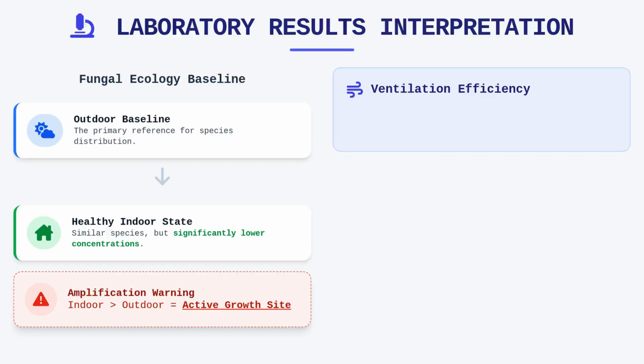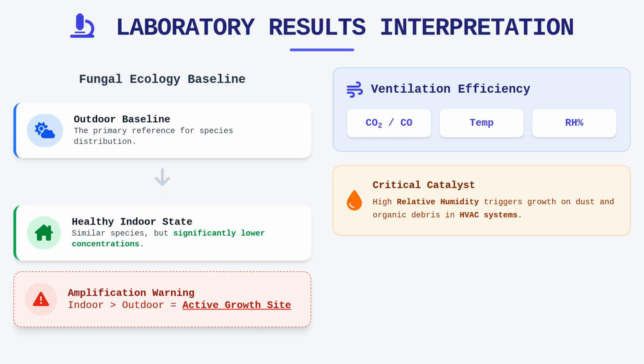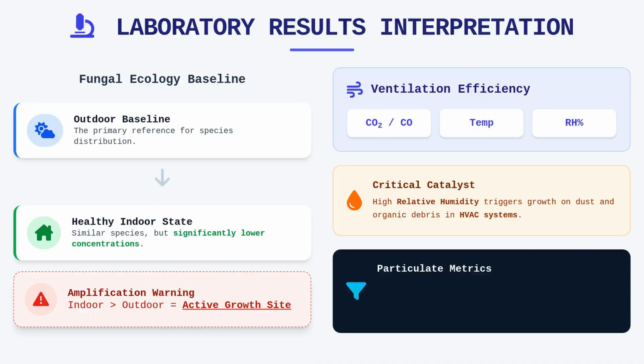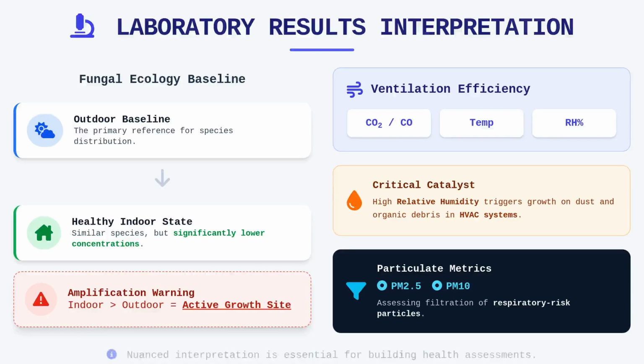Common indoor air quality parameters, such as carbon dioxide and carbon monoxide levels, as well as temperature and relative humidity, function as primary indicators of ventilation efficiency. Excessive relative humidity is a particularly critical factor because it serves as the catalyst for microbial growth on dust and organic debris trapped within the HVAC system. You should also be familiar with particulate matter metrics, specifically PM 2.5 and PM 10, which help assess the system's ability to filter fine, inhalable particles that pose significant respiratory concerns.